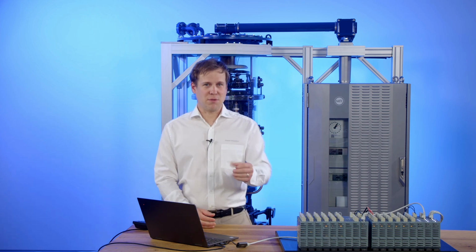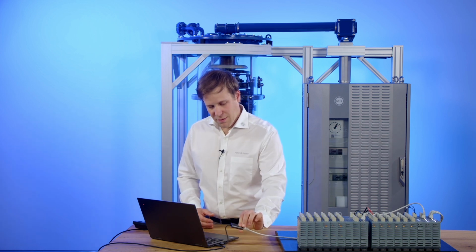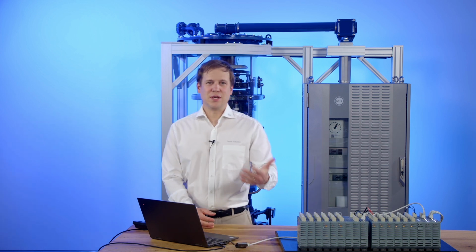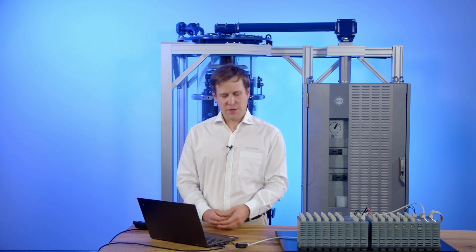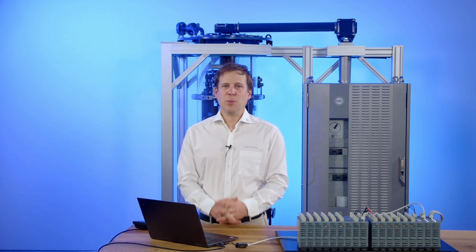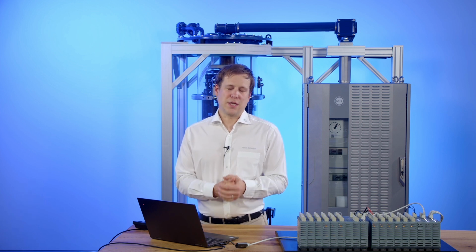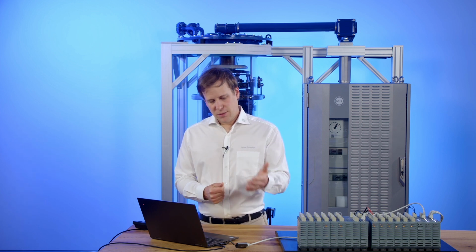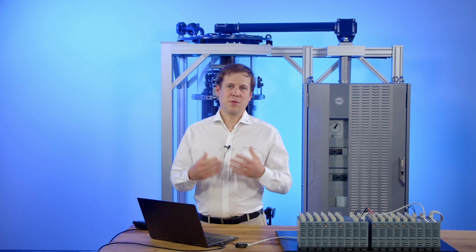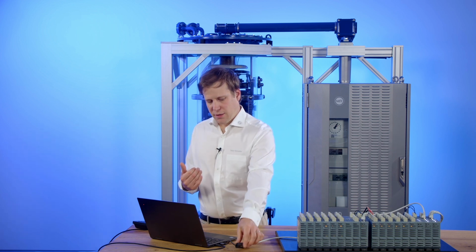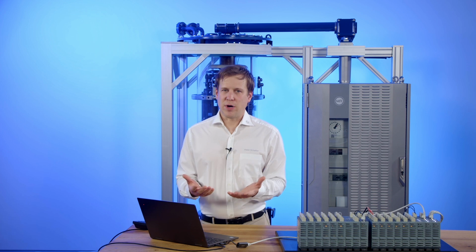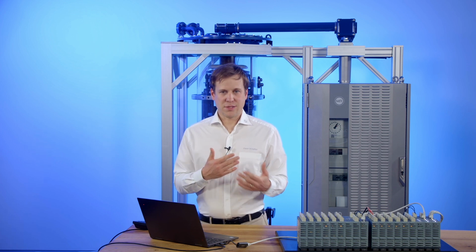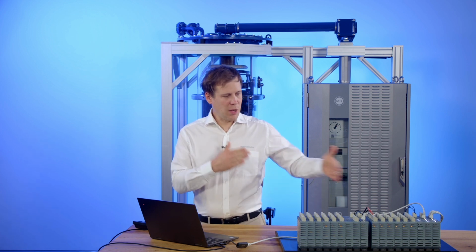First trick is right here on my table. Feel free to use a USB to Ethernet adapter. USB-A, USB-C to Ethernet, doesn't matter which one, but you can pre-configure this adapter very easily to always have the same IP address, and whenever I reconnect that specific adapter to my laptop, it'll always remember the last IP address settings. So I can use it as a plug-and-play connector for ETOS.